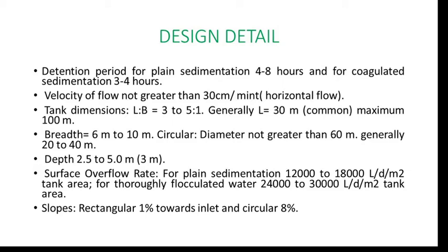The first one is the detention time. You all know what the detention time is. It is nothing but the theoretical period required for the settling of the particles or impurities. The detention period for plain sedimentation is basically 4 to 8 hours. That means a period of 4 to 8 hours is required for the settling of particles at the bottom of the basin.